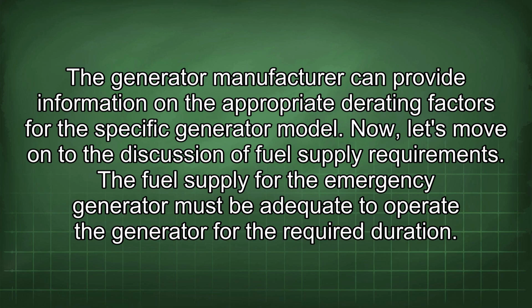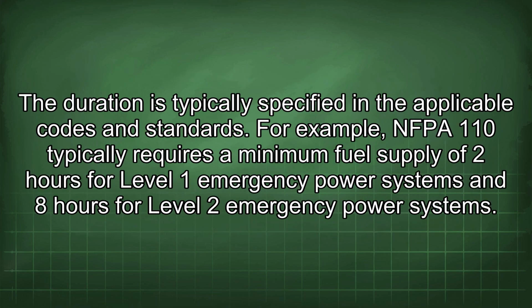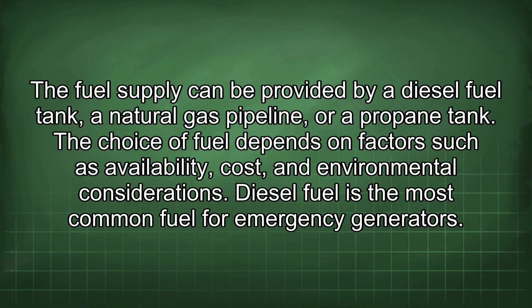The fuel supply for the emergency generator must be adequate to operate the generator for the required duration. The duration is typically specified in the applicable codes and standards. For example, NFPA 110 typically requires a minimum fuel supply of 2 hours for Level 1 emergency power systems and 8 hours for Level 2 emergency power systems. The fuel supply can be provided by a diesel fuel tank, a natural gas pipeline, or a propane tank. The choice of fuel depends on factors such as availability, cost, and environmental considerations.